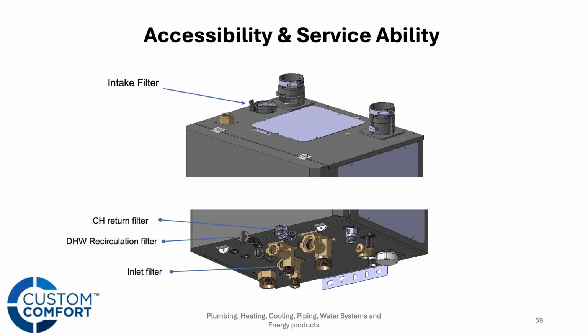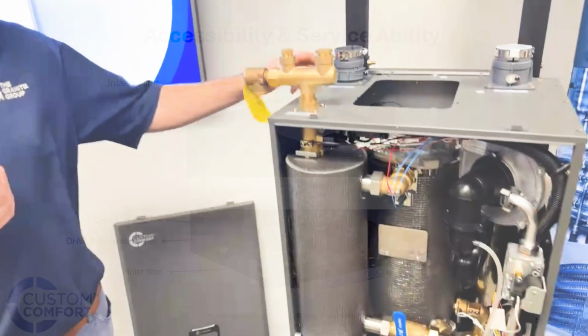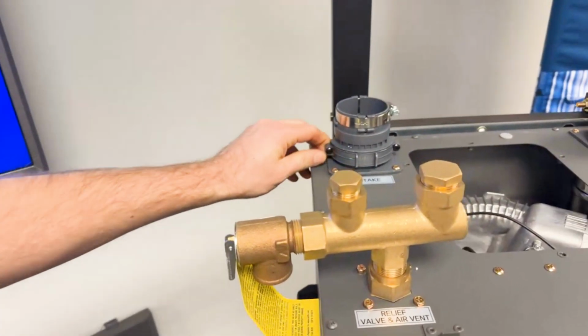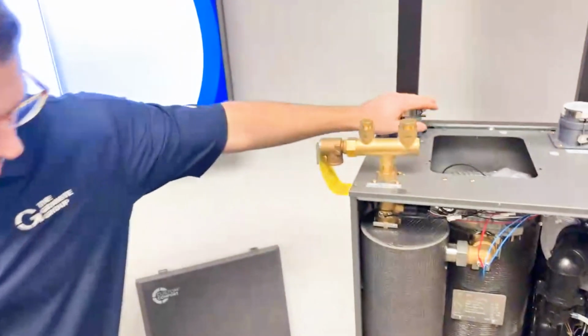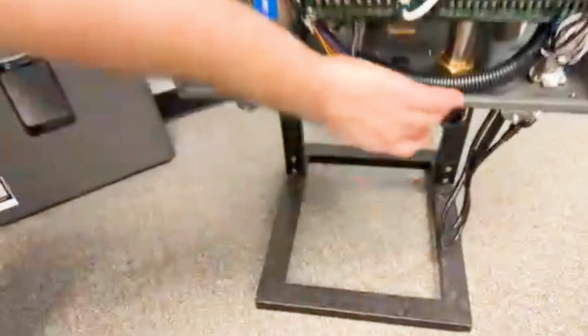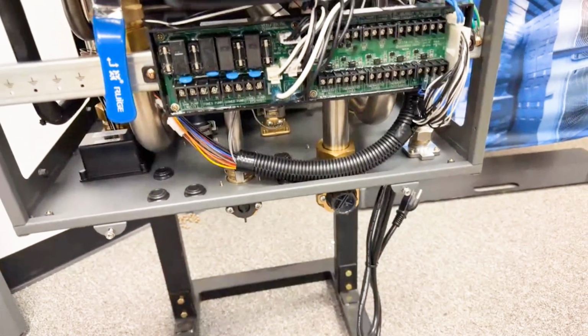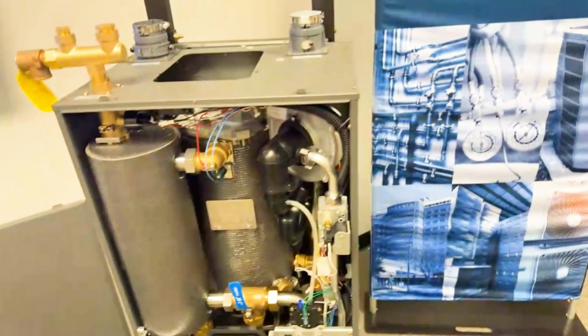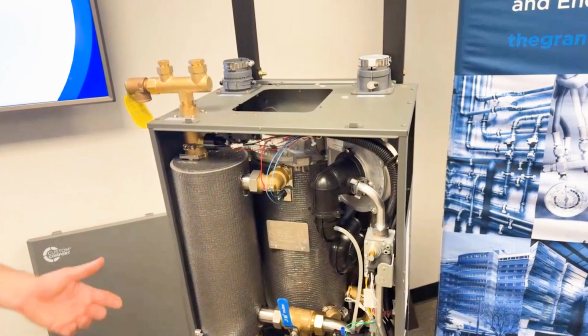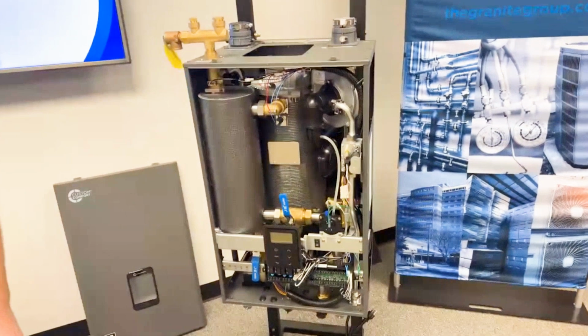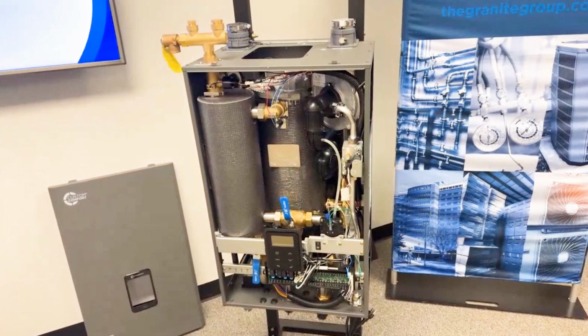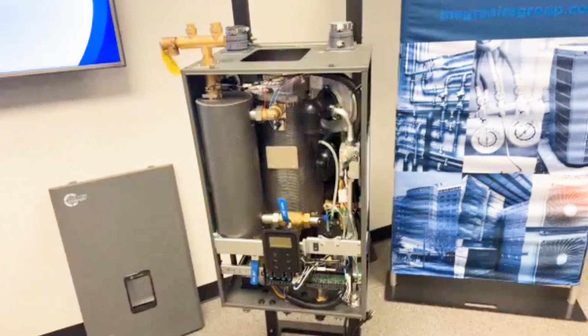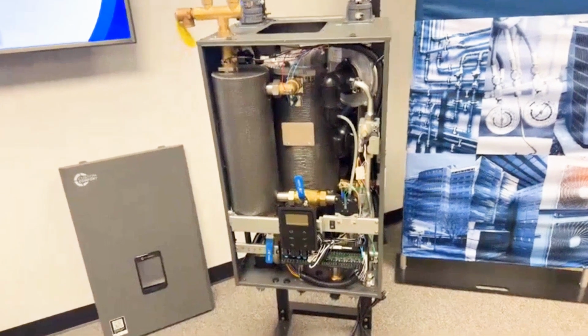So let's take a look at the boiler itself, the serviceability I mentioned before, and the accessibility of it, right? I think that's one of the best features of this boiler, how easy you can access anything on it. Starting on the top here, we've got the intake filter on the outside of the boiler, right? So you're not trying to squeeze in here and get to that. That's right on top. On the bottom here, we've got filters on the heating return, on the recirc, and on the domestic inlet. So we're trying to protect that boiler, or the heat exchanger on that boiler, right? If you're looking at annual service, stuff like that, it's a good idea to pop those stainless steel screens out, flush them out, and clean them if there's any debris in there. Again, you're going to want to have some type of air elimination, but I would also recommend dirt separation, or a magnetic dirt separator, to further protect the heat exchanger on this boiler.